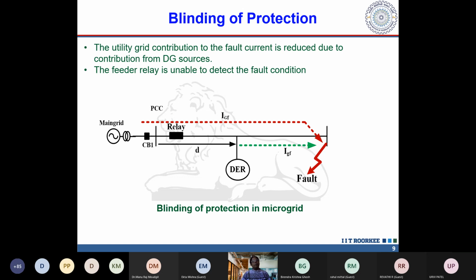Fine. Now when this fault occurs in front of this DER, what will happen? Both the main grid and the DER will contribute to the fault current, isn't it? Let us say the DER is not present and only the grid supplies the current. Then the relay will see more current. But as the DER is also contributing fault current, the contribution by the main grid will be reduced, and the relay will see less current.